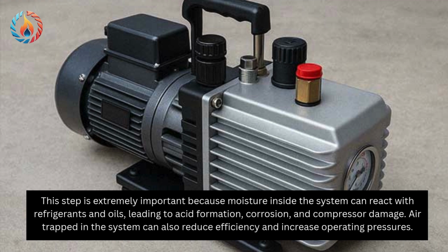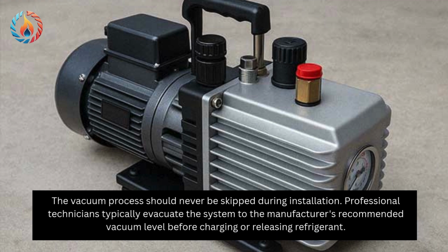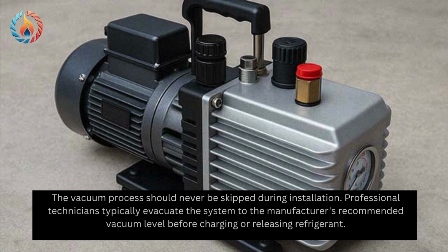This step is extremely important because moisture inside the system can react with refrigerants and oils, leading to acid formation, corrosion, and compressor damage. Air trapped in the system can also reduce efficiency and increase operating pressures. The vacuum process should never be skipped during installation. Professional technicians typically evacuate the system to the manufacturer's recommended vacuum level before charging or releasing refrigerant.